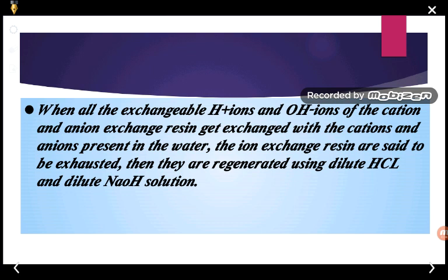So when the H plus ions and OH minus ions of the cation and anion exchange resins get exchanged with the cations and anions present in the water, the ion exchange resins are said to be exhausted, and they are then regenerated using dilute HCl or NaOH.